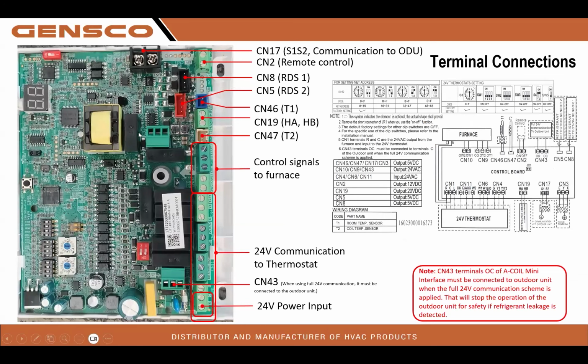Let's take a look at that mitigation control board real quick. Here are our 24-volt controls. Here's our S1, S2. If we're going to be fully communicating, this goes out to the outdoor unit. Here's our mitigation controls. This goes to our refrigerant leak detector, and that refrigerant leak detector must be plugged into CN8, the black plug, not the red plug. Here's our T1 sensor, our return air sensor. It must be plugged into the blue plug. The T1 sensor does have a blue plug on the end of it. It is color-coded. Control signals to the furnace are 24-volt thermostat connections and 24-volt power.